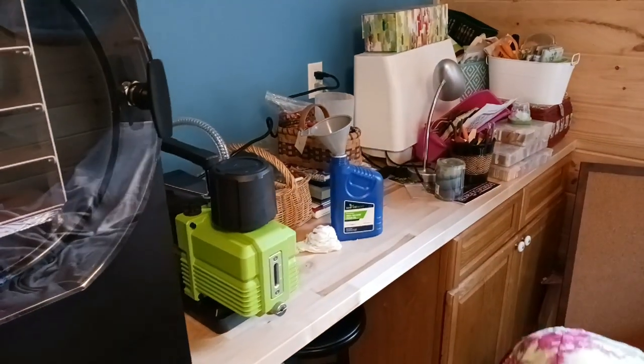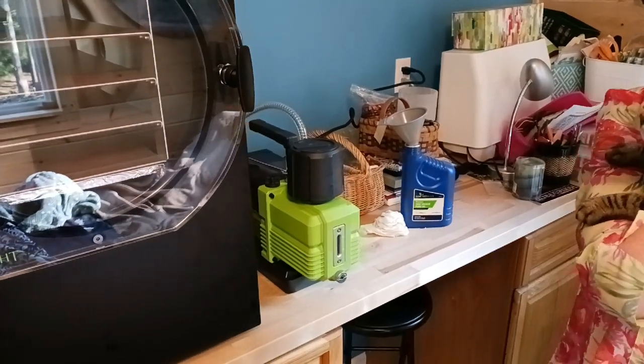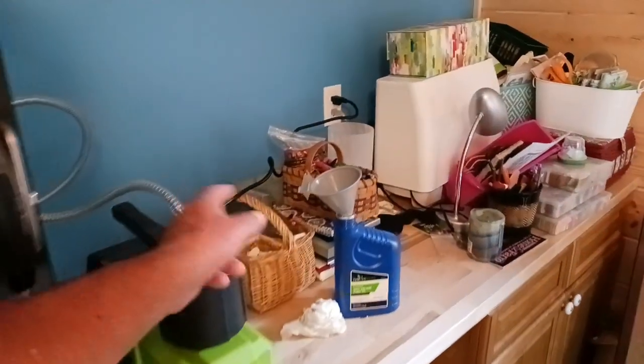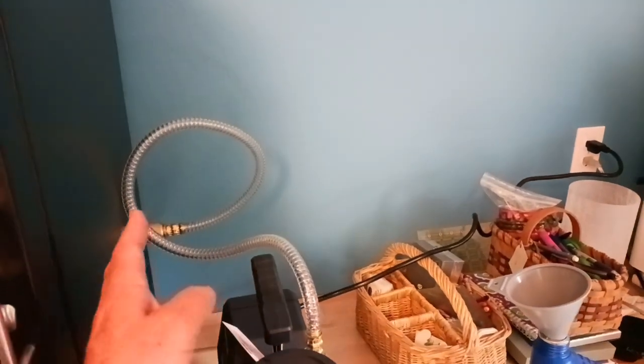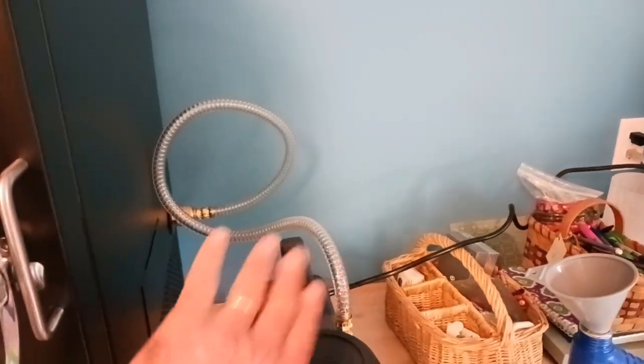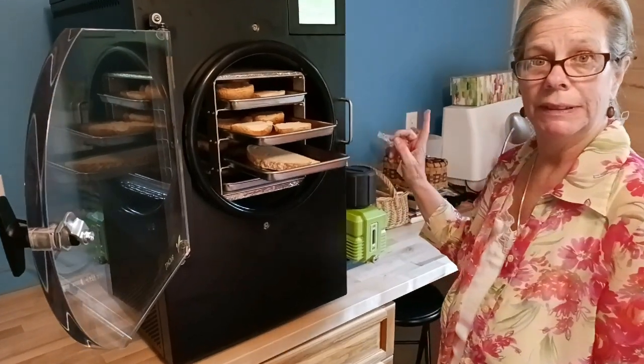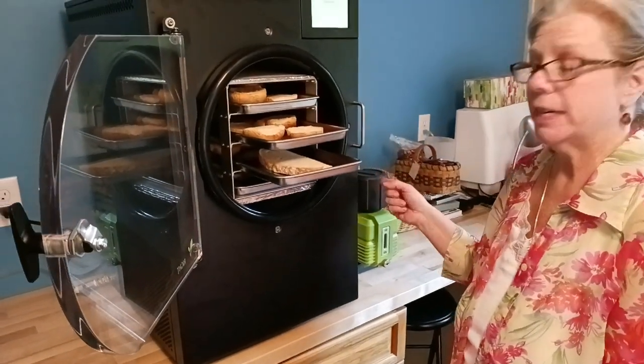The setup is — once you do it, I think you can do the whole thing in five minutes. Add oil, put your vacuum hose connections, get your power cord to the harvester, plug your pump into the back, put your drain hose on — and that's really it. We've got the pump filled with oil, had it cycled through, so it's ready to go.